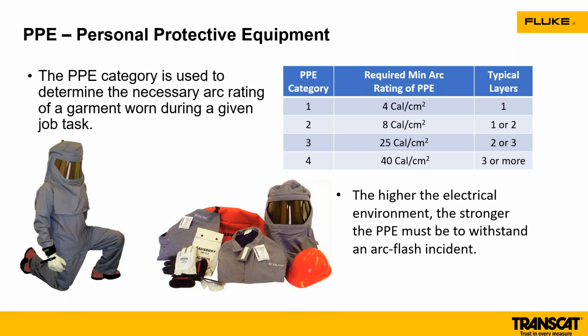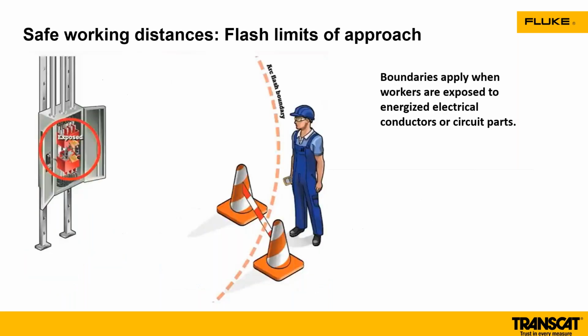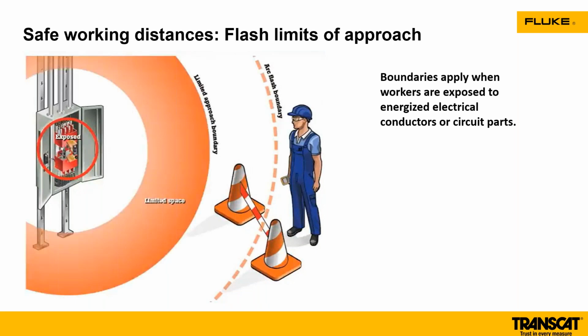So when we start talking about your PPE and those category ratings, depending on where you're working, there are limits, these flash limits of approach. These are boundaries set up. The higher the energy, the larger the circle should be around your exposed environment. There's an arc flash boundary, and basically anybody who wasn't trained to be in that area would be out on the farthest boundary possible. It's just allowing these people to walk past, but if something happened, you wouldn't allow them to get within that boundary. The next boundary is your limited approach space, and that's where we would want to make sure that people are trained, they're certified, they would have the correct PPE on to be able to get into that.